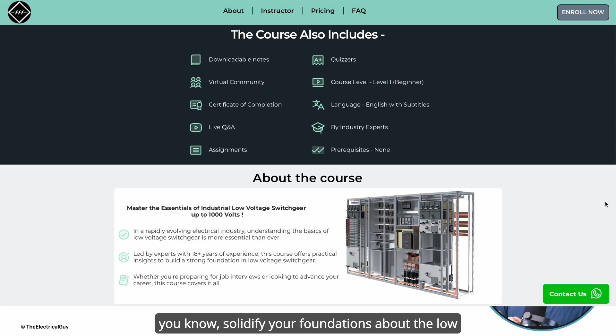So everything put together, the ringmain unit, the medium voltage switchgear, the transformer and the low voltage switchgear put inside a container is what we refer to as the package substation or prefabricated substation. Why prefabricated? Because it comes from the manufacturer directly to the customer with everything installed at the factory, pre-assembled. You just have to put it on site, give the connections and initialize it, so the installation time reduces drastically.